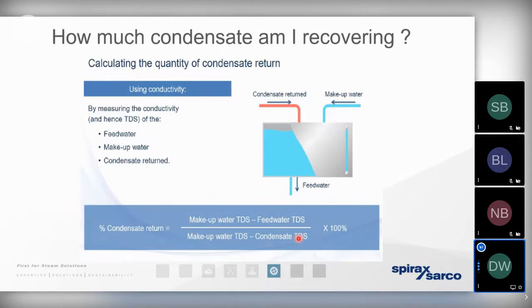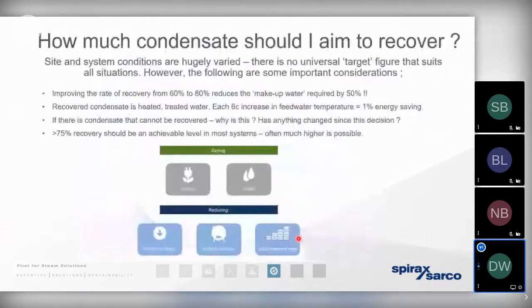So the next question is, well, what should I be aiming to recover? What does good actually look like? A typical rule of thumb is we should be aiming to recover somewhere between 60 to 80% of all of the steam that's been distributed as condensate. So, for example, if we're generating 10,000 kilograms per hour of steam, we want to be aiming to recover about 8,000 kilograms per hour of condensate.